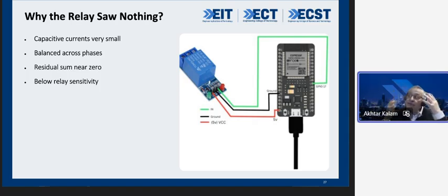So this protective relay failed to detect this single line to ground fault, and this is a challenge faced by electrical power systems on a daily basis, typically stemming from the fault characteristic not meeting the relay's threshold. The relay may see nothing because the fault current is too low. You can't blame the relay. The system grounding is ineffective or the fault is intermittent. And as I mentioned, it is because this is a high resistance fault. It could be because of the system grounding configuration, relay setting and sensitivity, or technical and physical limitations, and all that sort of thing.